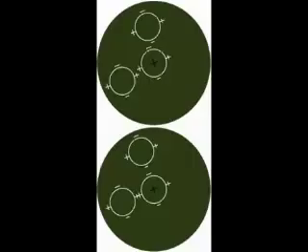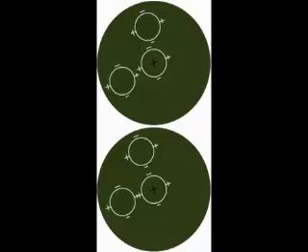You will see two plus signs between the left-hand circle and the focusing circle. To locate the axis of the corneal astigmatism, turn the rotating grip knob so that the tips of the plus signs touch. If the patient has regular astigmatism, remember this is when the principal meridians are 90 degrees apart, the minus signs will align vertically. If the minus signs do not align vertically, the patient has irregular astigmatism. Remember, irregular astigmatism is when the two principal meridians are not 90 degrees apart.